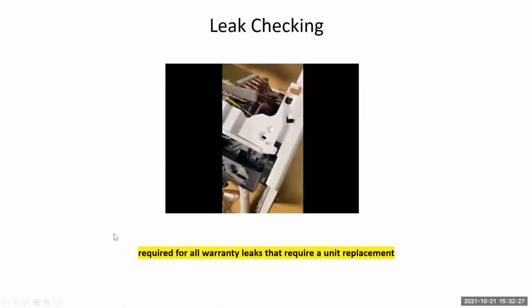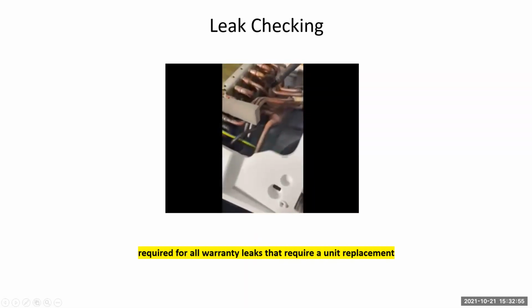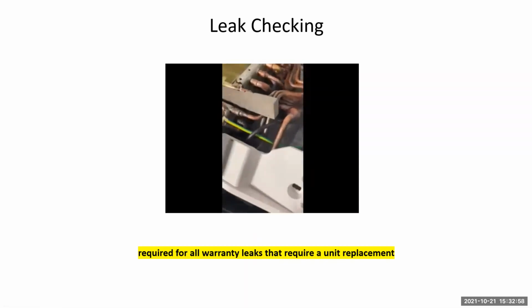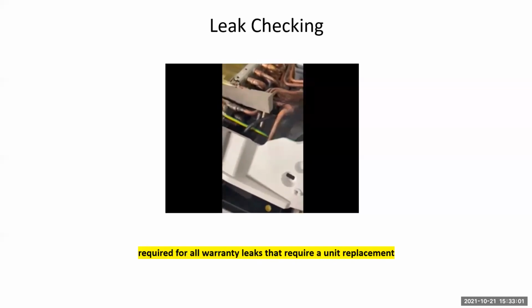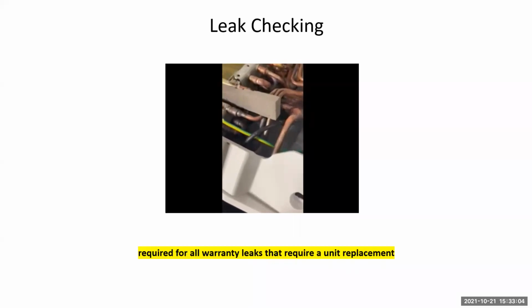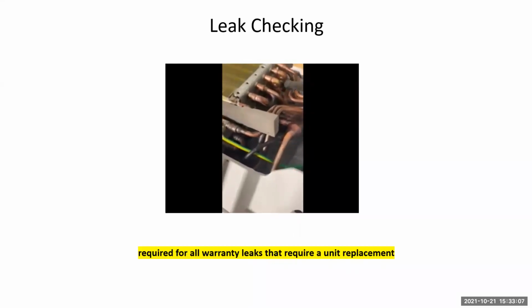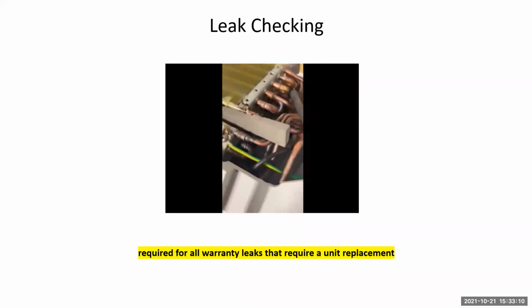So this comes from up at Carrier. They're requiring either videos or pictures of all leaks on any coil. And that used to be just with ductless, but that's not with just ductless anymore. As many of you know, that's also with all evaporator coils and condenser coils. They want either a nice video like this or soap bubbles. It's very difficult to get a unit replaced without a picture of the leak or a leak detector like this.